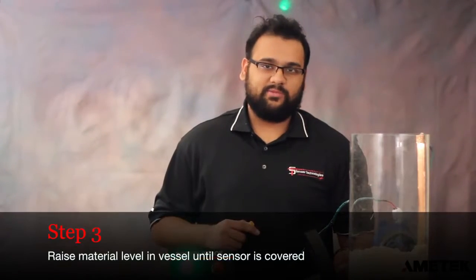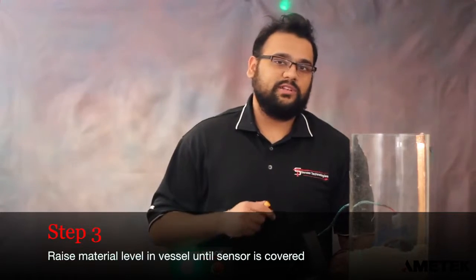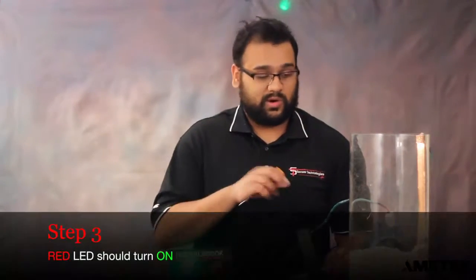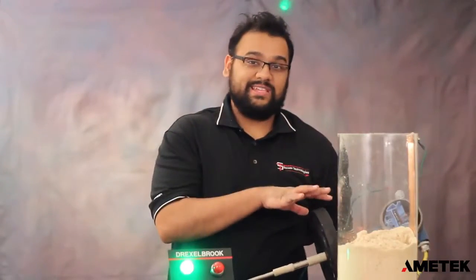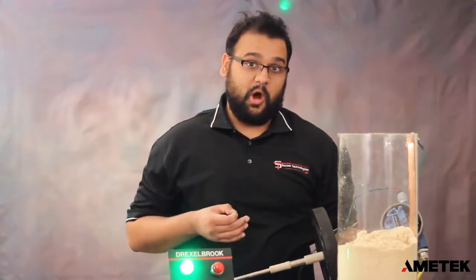Okay, now for the last step of the calibration procedure, you want to raise the level in your tank to where you want your trip point to be. So in our little tank here, we have about 8 inches of sawdust. We're going to take our probe and insert it into the tank, and the red LED should come on.